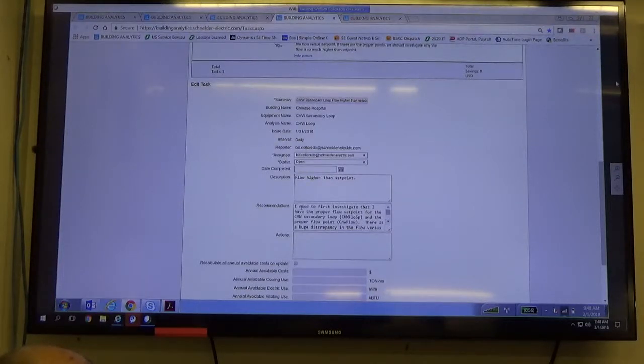With my notes here in the recommendations, I need to first investigate that I have the proper flow set point for the chill water secondary loop, which is this point name, chill water flow set point, and the proper flow point is this point name. There's a huge discrepancy in the flow versus the set point.